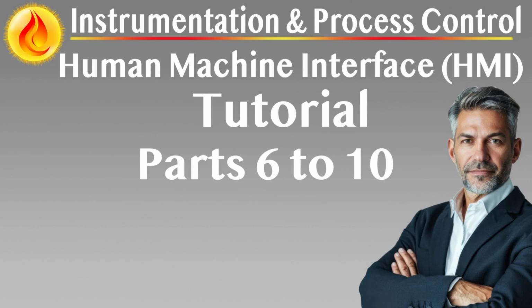FGS Mimic Panel. A dedicated mimic panel should be included for fire and gas system (FGS) displays. While most alarms are presented on the DCS, FGS hardwired panels remain necessary due to regulatory and safety requirements. These can be integrated into the main console or mounted separately, but must be clearly visible and accessible during all plant conditions.